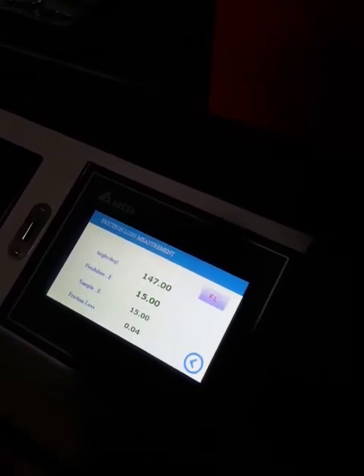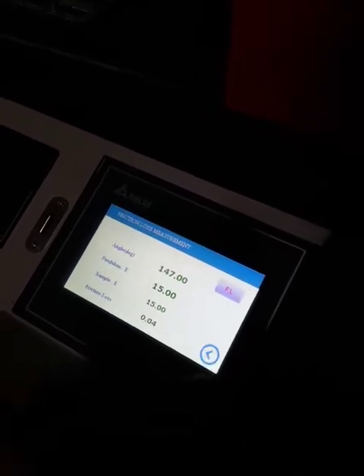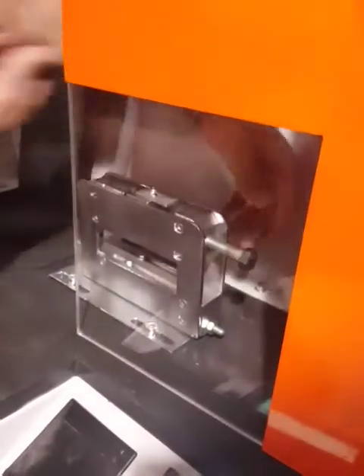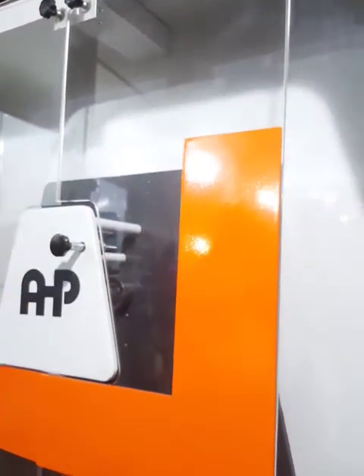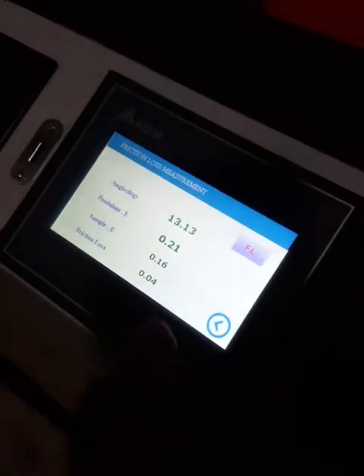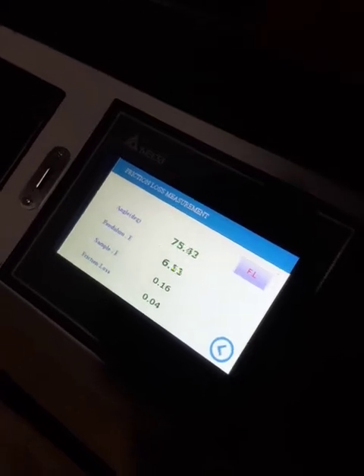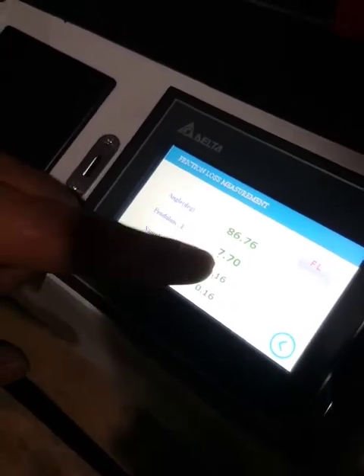That's all. Then we need to go to the next page for calibrating the friction loss, for calculating the friction loss of the machine. Just open the door. It should be without any kind of sample, and the pendulum is in the upper position. We are in the friction loss measurement page. For measuring the friction loss of the machine, the only thing is to release the pendulum. After that, the machine will calculate the friction loss. It shows the sample energy. This is not a real sample energy, it's the friction loss of the machine. Then we need to click on FL, then the friction loss is saved for the machine. Now everything is calibrated.